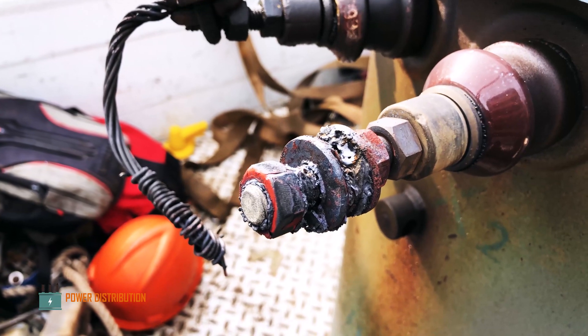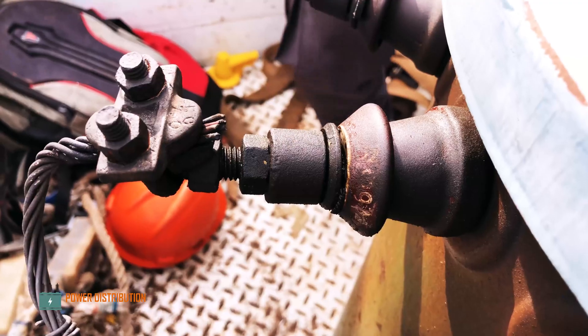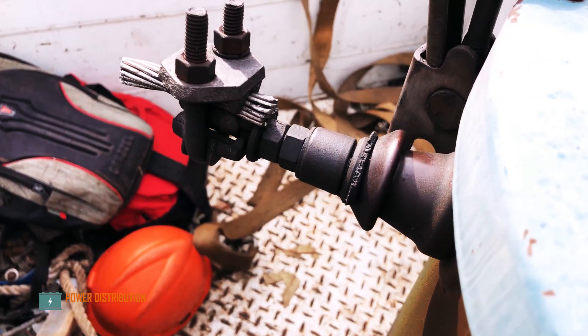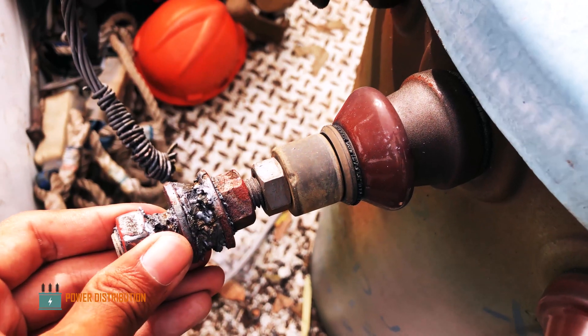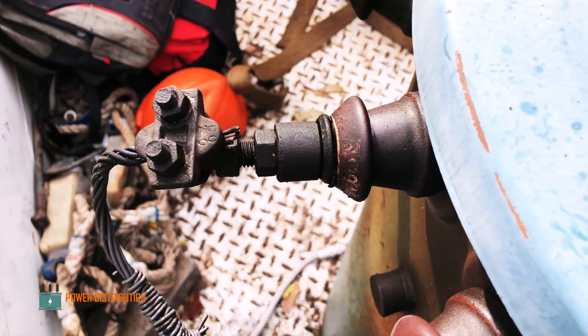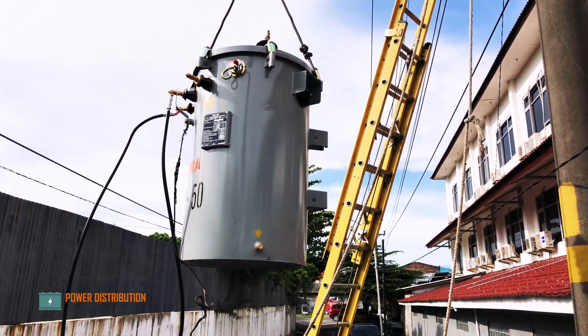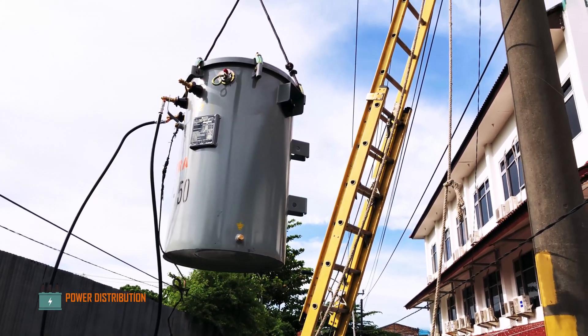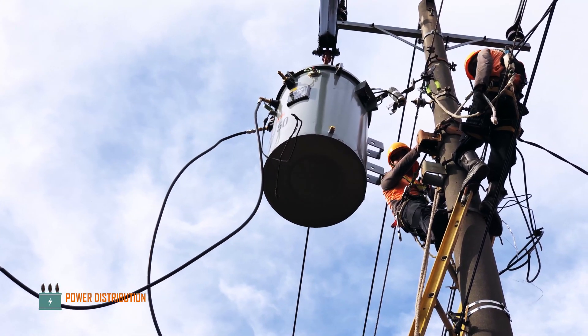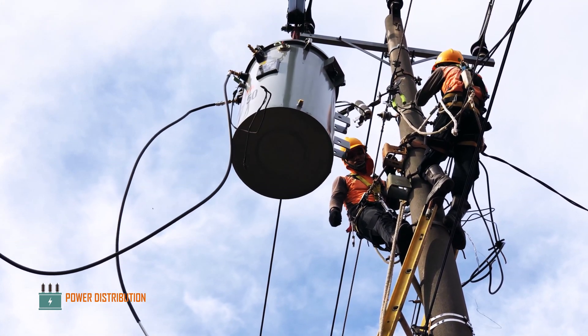As you can see, a significant amount of melted wire has fused into the secondary bushing. Significant arcing from the bushings indicates the insulation has been compromised. The new shiny transformer is now being lifted and is ready to be installed with the new bolts.